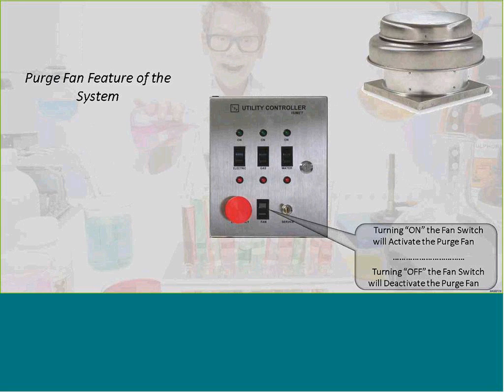Now, if you hit the panic button and you are in your high-speed fan, the only way to shut that off is to reset the system with the key, and then that will set it to normal operation again. As long as the panic button has activated the fan, your switch is not operable, because we want to make sure that the only way that fan shuts back off is when you reset the system, because then your emergency is over.